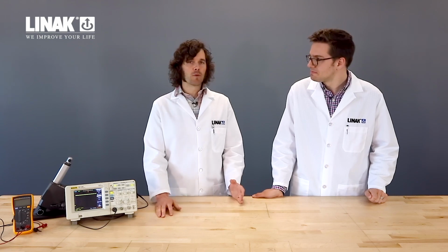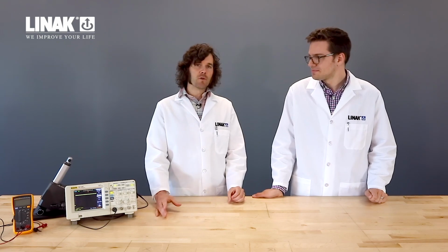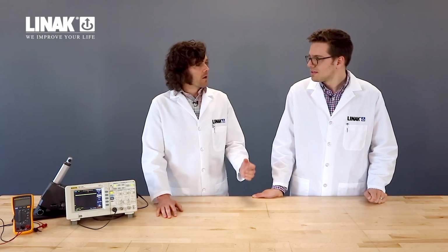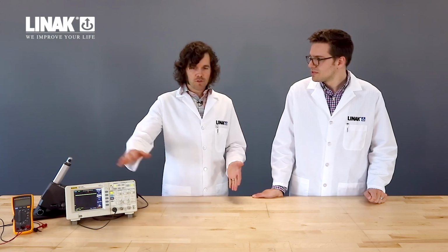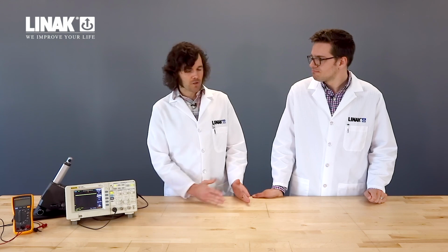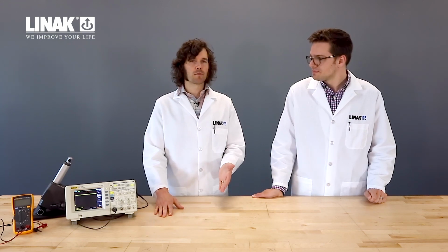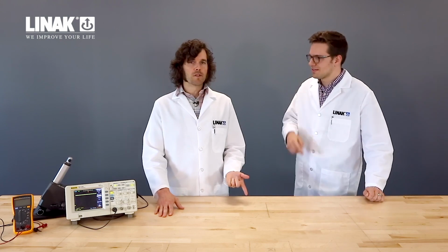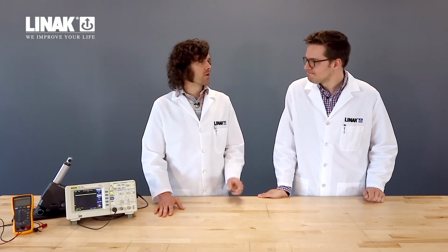That's right. Probably the most common one would be, say, 0 to 10 volts, where the scaled voltage difference would be specific to some percentage of the actuator stroke length. That's right. This type is susceptible to noise and voltage drop over long cable runs.